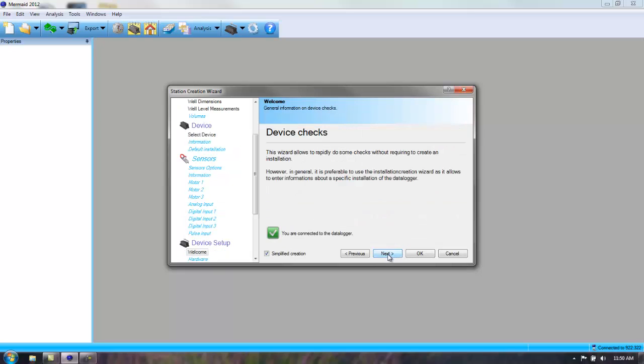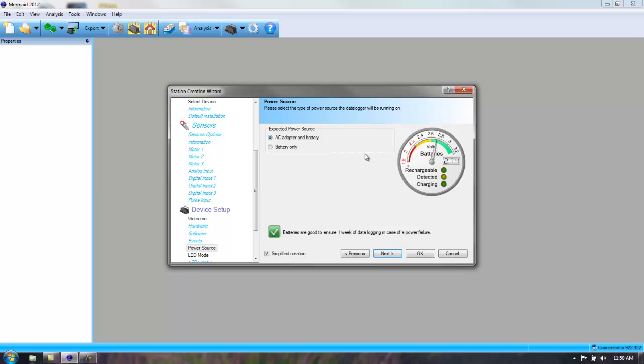Check device screen, just hit next for this one, and you notice it will actually check your battery voltage that you have inside the unit, and it also asks you what your expected power source is going to be. The MerMaid system was designed and intended to use an AC adapter as power input and a battery as a backup. But you can monitor a station for a short time on batteries only. That's going to depend on the frequency of the pump running and the data being collected, but typically you can get away with 3 weeks, sometimes a little bit more on a station on batteries only.